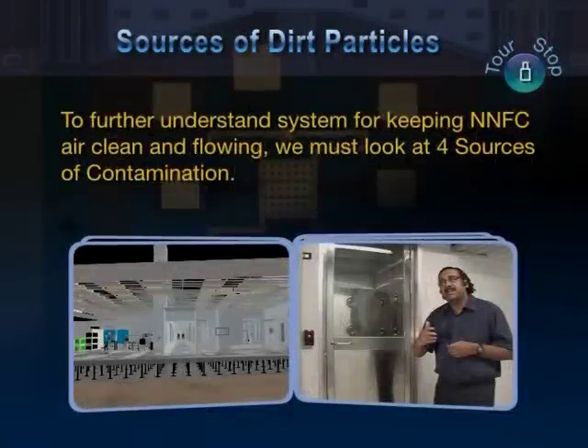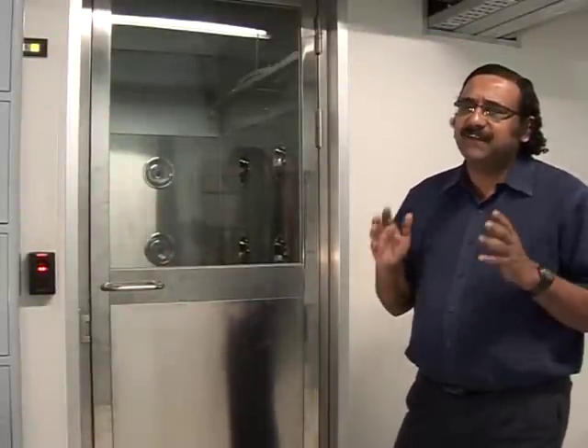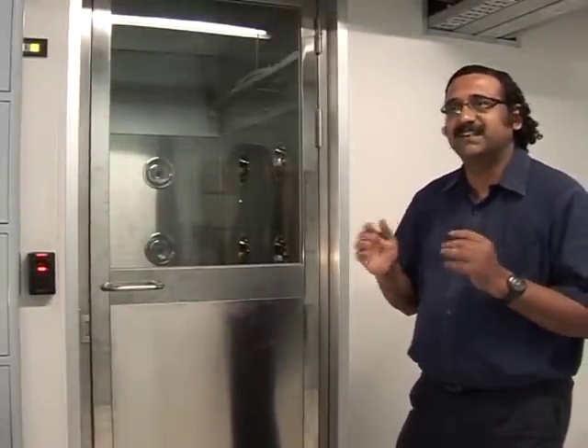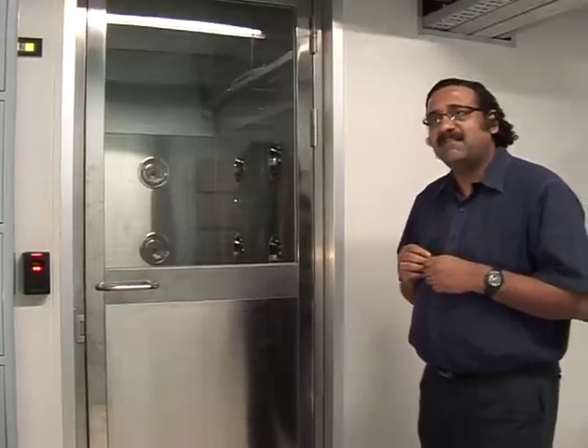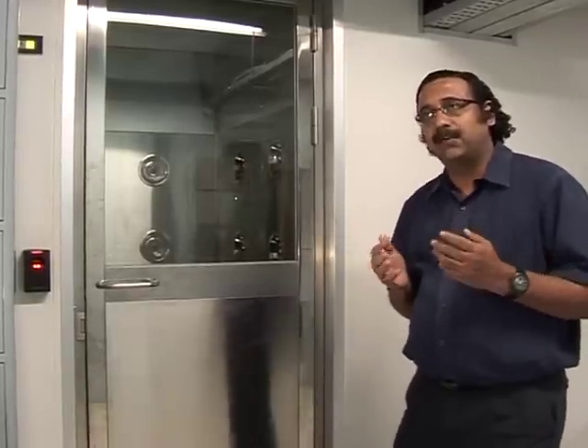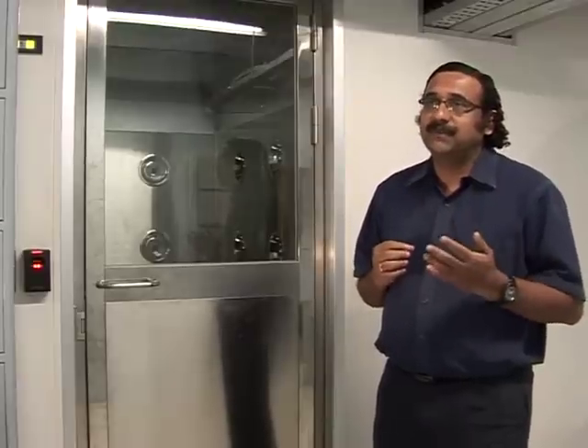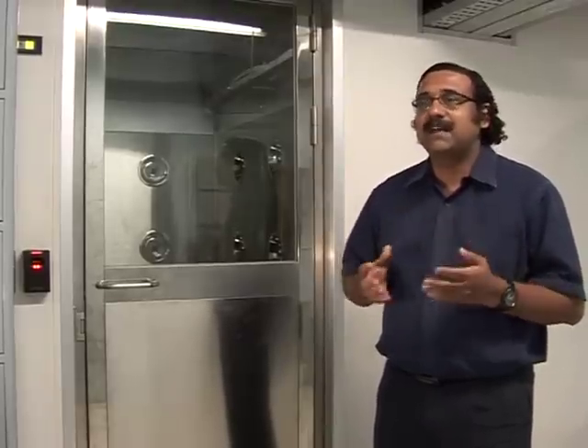To further understand the multi-featured system designed to keep NNFC air clean and flowing, we must know about 4 sources of contamination that bring dirt particles into the clean room. Now, I will explain about different sources of contamination in a clean room facility and also about the airflow pattern inside. There are 4 major sources of contamination in a clean room. The first one is coming from the people. We are one of the biggest sources of contamination.